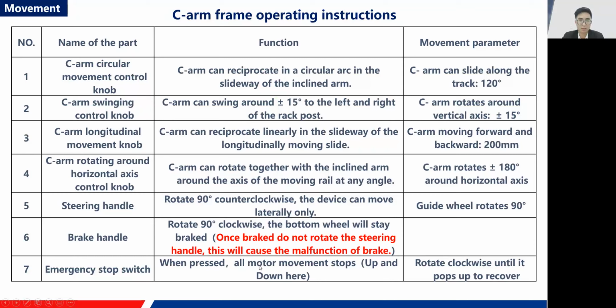Of course, when pressed, all the motor movement stops. For our 112B, the up and down movement is electric, driven by our motor. So when the emergency stop switch is pressed, the up and down won't function, right? Just rotate it clockwise, and the emergency stop switch will pop up, and that means the movement can continue. It is recovered, right? You could try that.